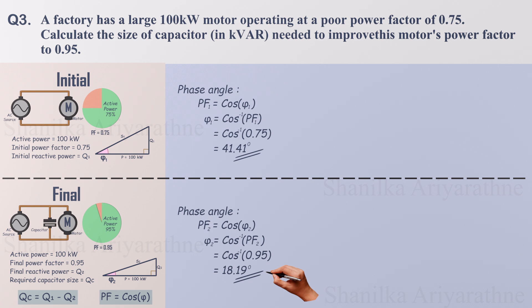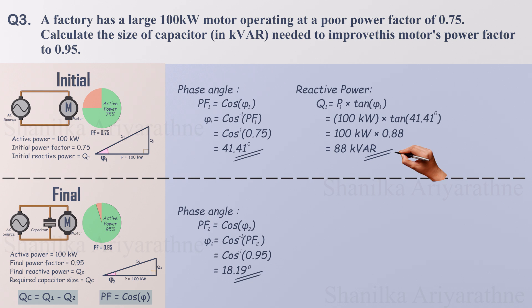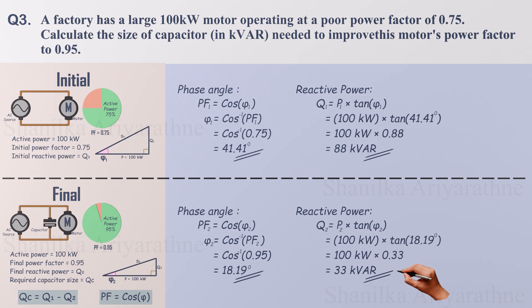Since we have two parameters of the power triangle, now we can calculate every other parameter. Let's calculate the initial reactive powers for both cases. Q1 is 88.2 kVAR — this represents the reactive power currently consumed by the motor. Q2 is 32.9 kVAR — this is the reactive power that should remain after correction.